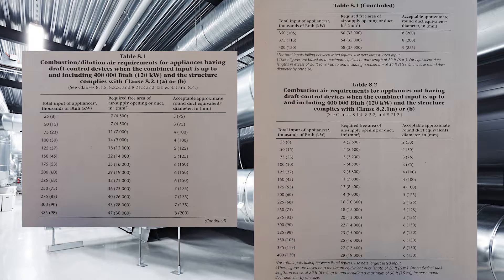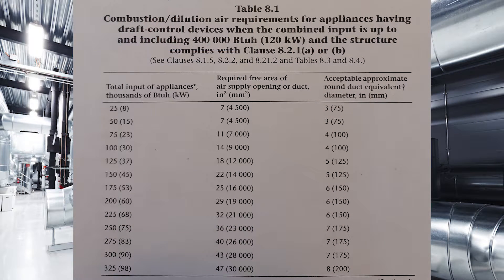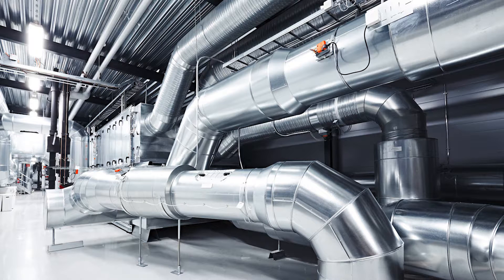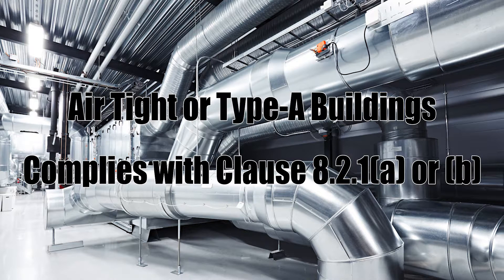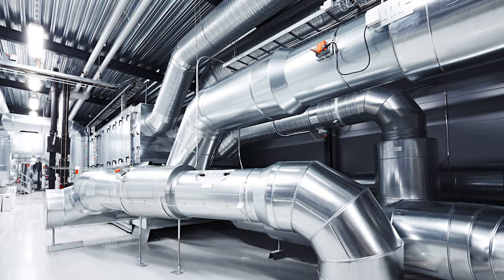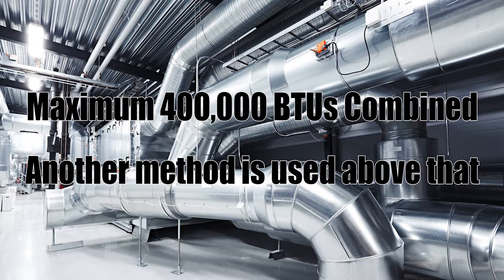We're going to be looking at tables 8.1 and 8.2 out of the gas code, which start on page 84 and go to 85. Table 8.1 says combustion dilution air requirements for appliances having draft control devices when the combined input is up to and including 400,000 BTUs (120 kilowatts) and the structure complies with clause 8-2-1A or B, meaning the building is built airtight or it is a type A building. These tables only go up to a combined input of 400,000 BTUs; anything above that needs to be sized a completely different way, which won't be discussed in this video.